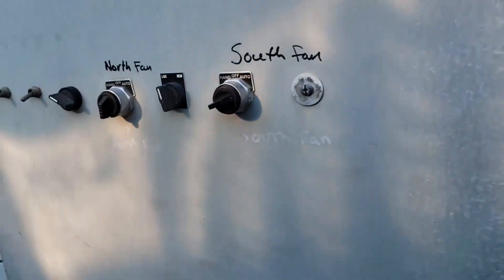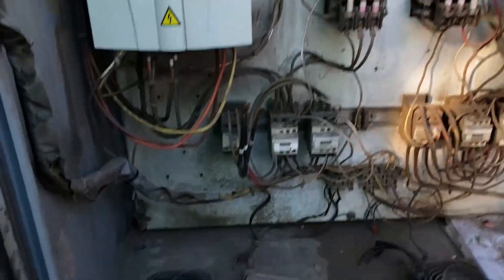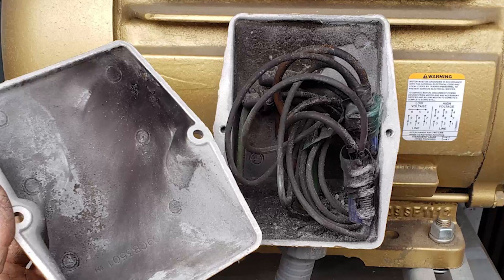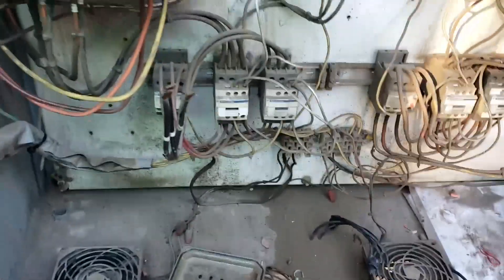This panel has been reworked a few times from its old controls — there's a really old panel over there. Some VFDs have been added. This one fried and seized; the motor wires in this pretty new tower had shitty connectors and they fried. I think I showed a photo of that. So this thing needs work.